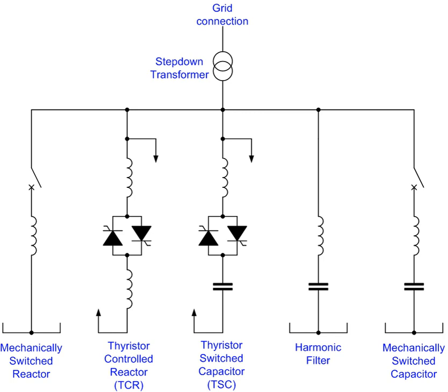Thyristors, like all semiconductors, generate heat and deionized water is commonly used to cool them. Chopping reactive load into the circuit in this manner injects undesirable odd-order harmonics, and so banks of high-power filters are usually provided to smooth the waveform. Since the filters themselves are capacitive, they also export MVARs to the power system.